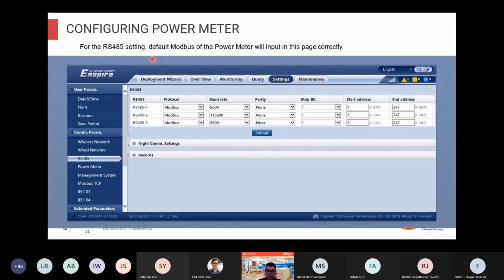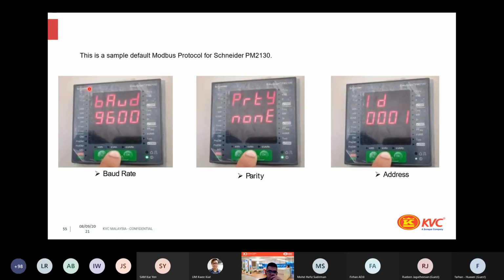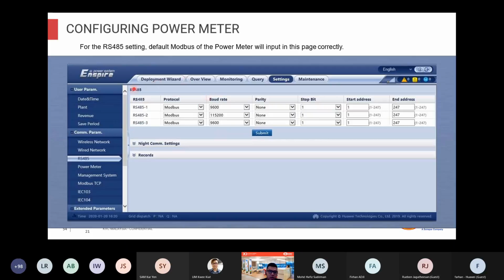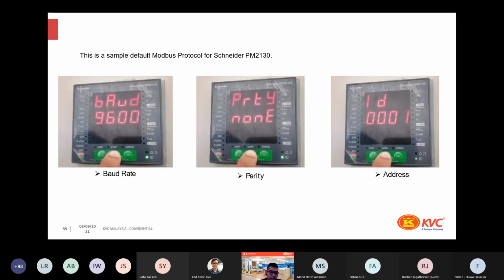If you look at the physical picture of the power meter, always make sure the baud rate, parity, and stop address are the same as your Smart Logger. A lot of times customers can't find their power meter because the RS-485 Modbus register list differs from what's on the power meter screen.